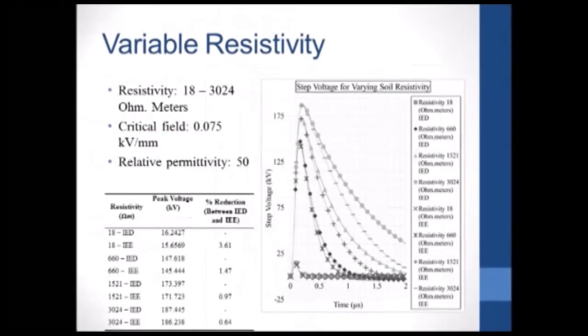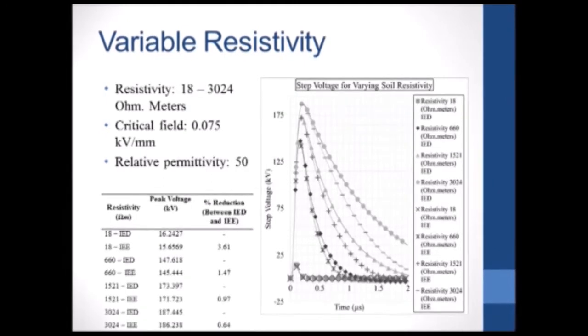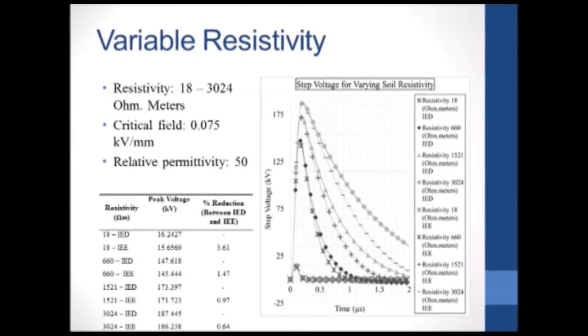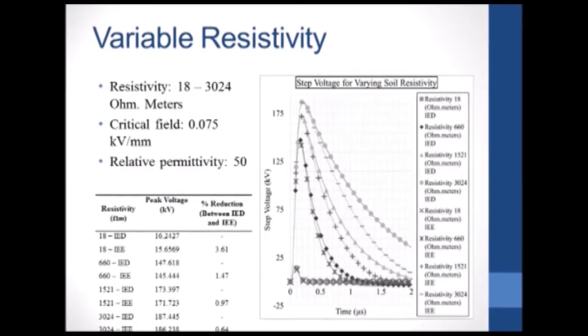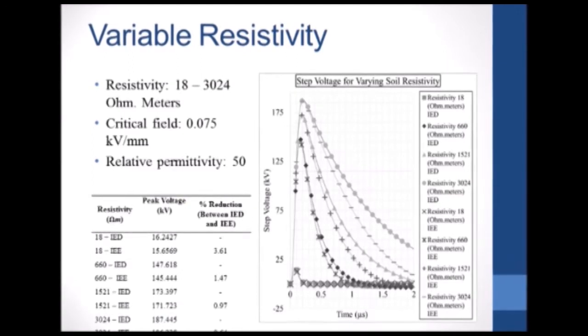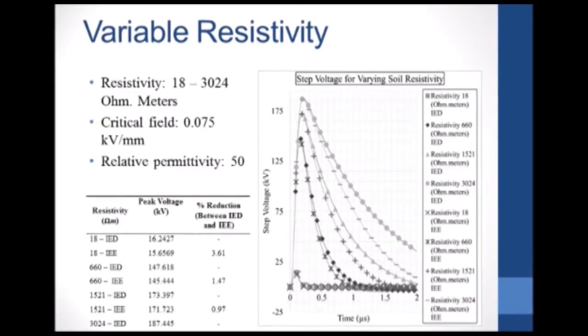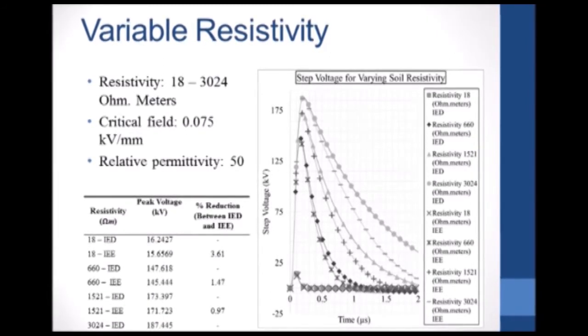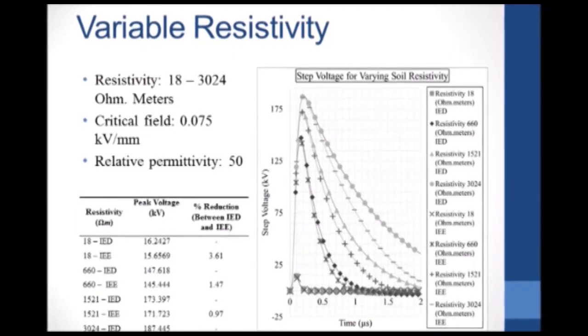For the variable resistivity run, the resistivity was increased from 18 to 3,024 ohm meters in steps of three. The critical field was set to 0.075 kV per mm, which is the worst case scenario for ionization onset, and the relative permittivity was fixed at 50. As you can see from the table, the effect of soil ionization again seems to be reduced with increasing resistivity.